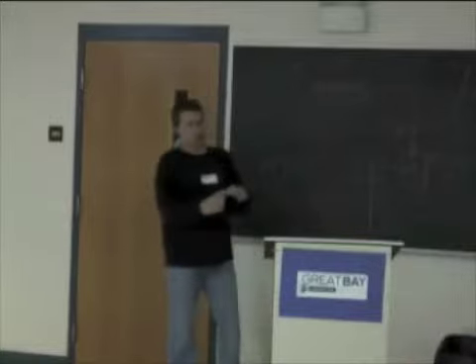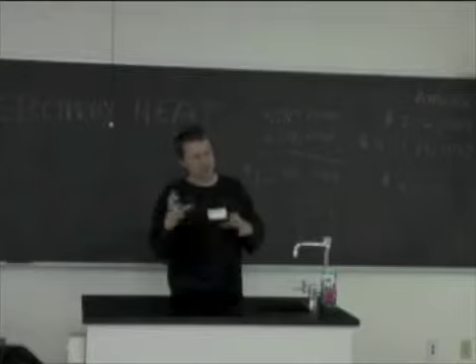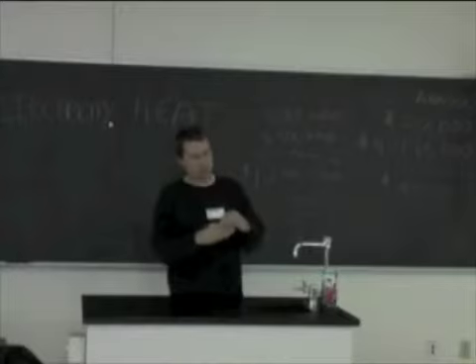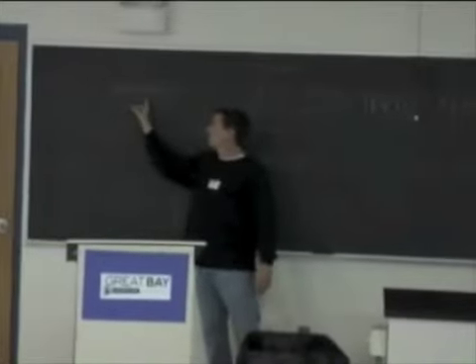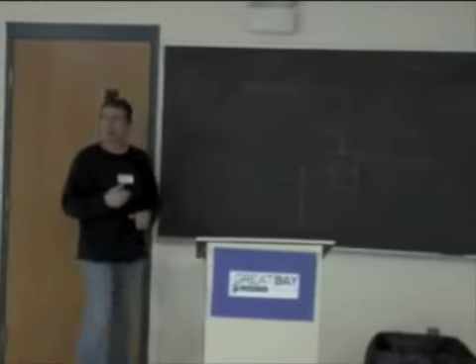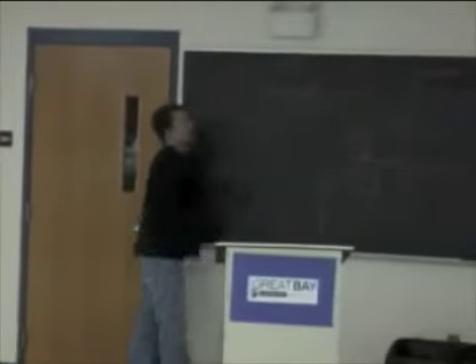What you have is an evacuated tube, and in it is a flat black metal sheet. In the center of that sheet is a tube with glycol in it. When the sun shines, even though it's 30 or negative 30 outside, because it's a vacuum, there's no temperature loss in here, and that black metal heats up. In fact, some of these systems have to have heat dumps on them because the glycol gets up to 190, 200, even 230 degrees, and you can end up with a blowout on one of the clamps.